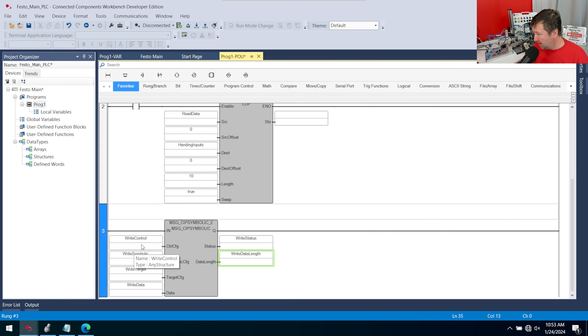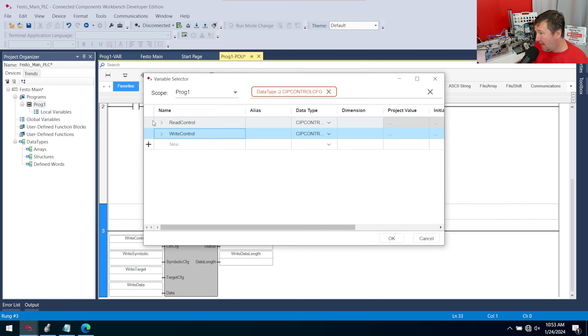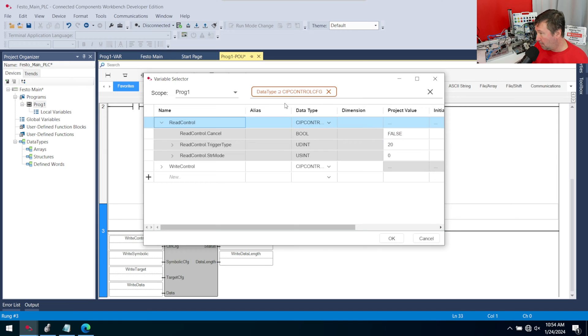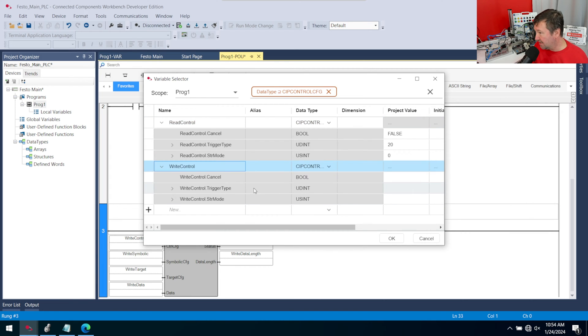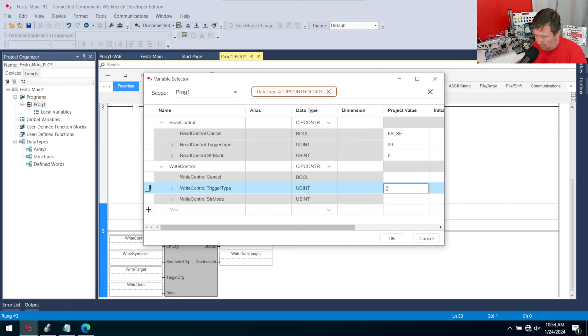For most of these, we can look at our read and find out our write settings. Let's double-click into them and open up our read control. Mainly we have our trigger type, which is how many milliseconds between each time you want to write this data. If we put it at zero, it's only going to trigger when this message instruction becomes true. We're just going to use the same 20 milliseconds that we used on our read.